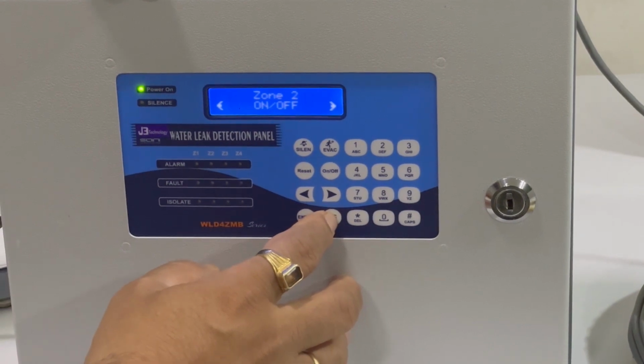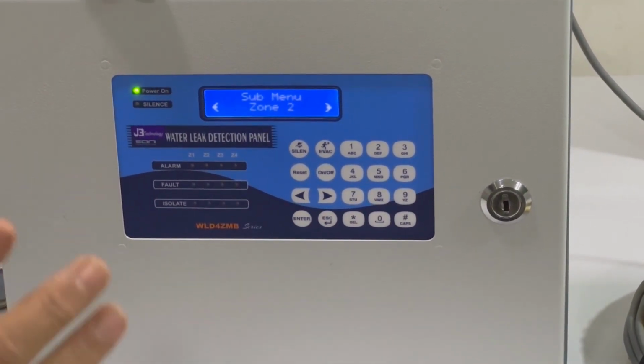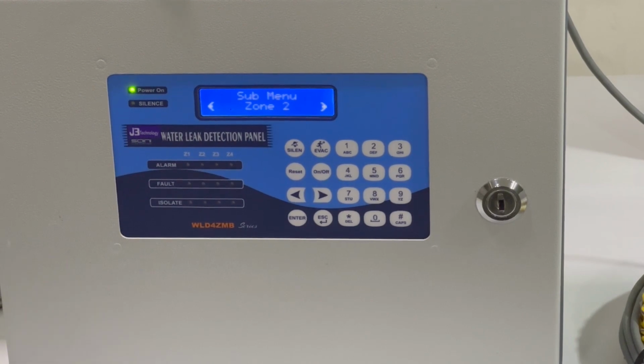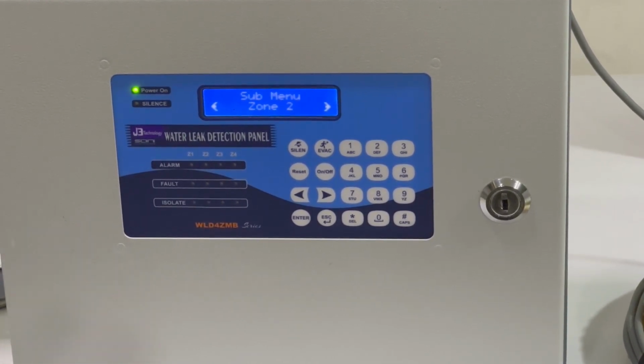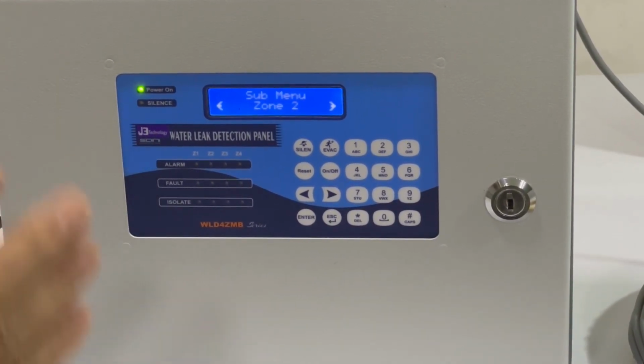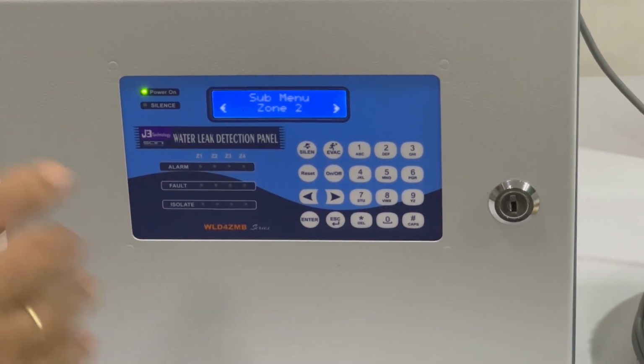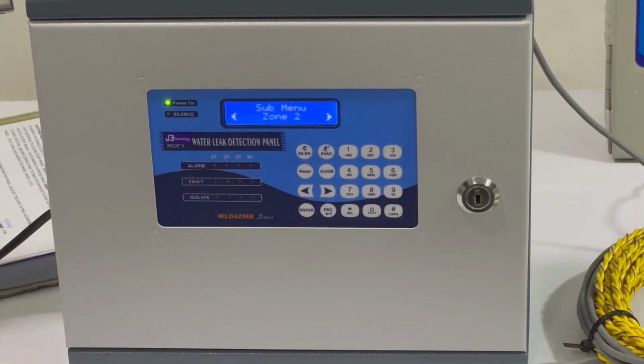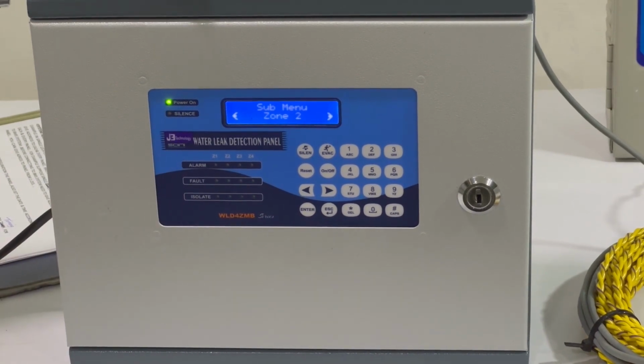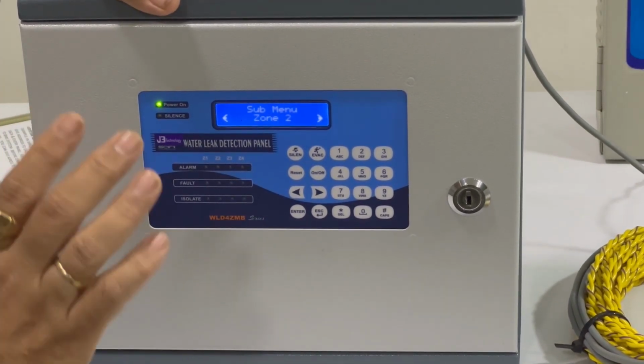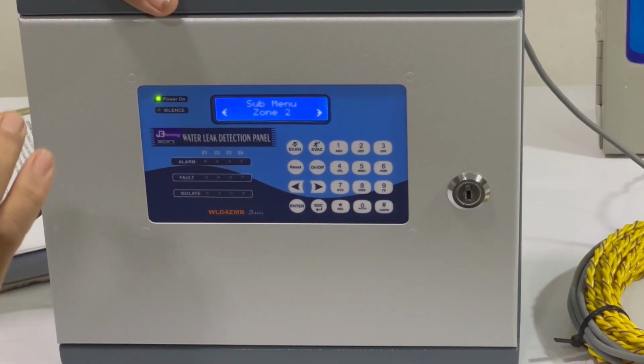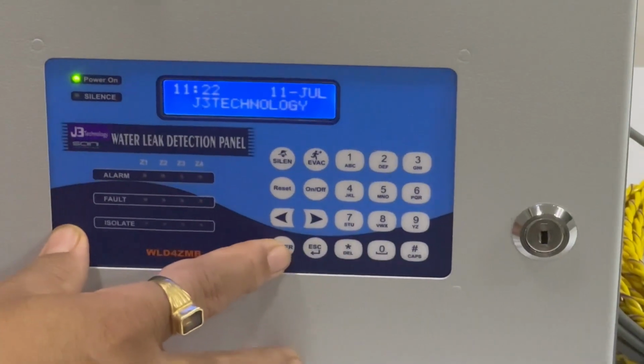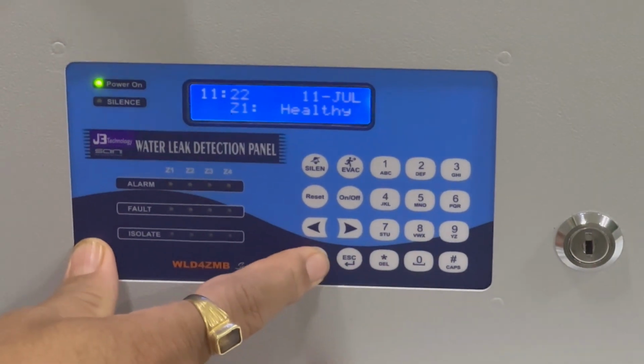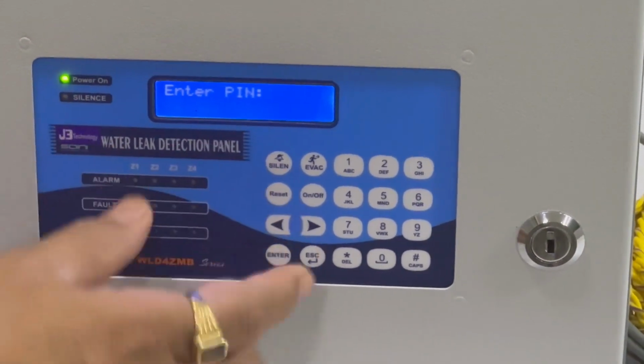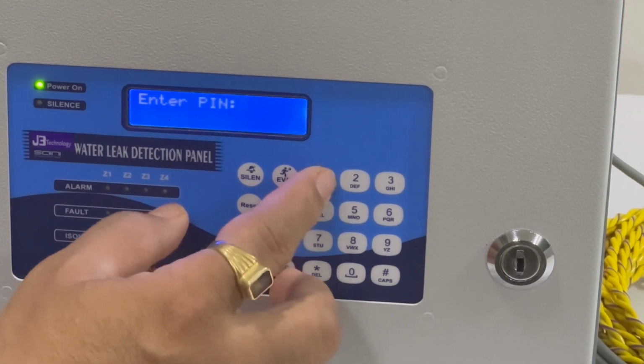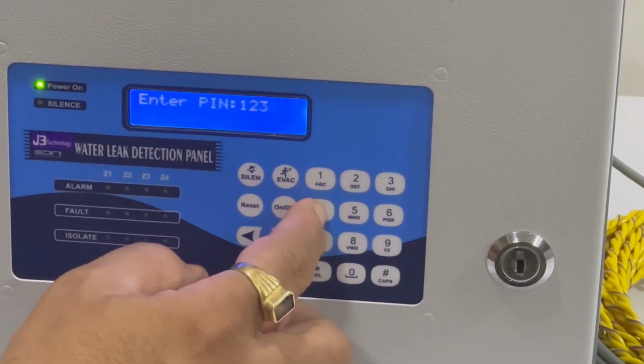So friends, this is a very important part that you have to do while installing the panel. Make sure how many zones you are going to use. According to that, you should keep those zones on and the remaining off. Or if you do not do this, then the panel will continually show you the fault. So in this case, you have to go to zone setting and set the zone to off. I will show you another second feature of this panel. Just click on enter. You have to put the password, which is 1 2 3 4.